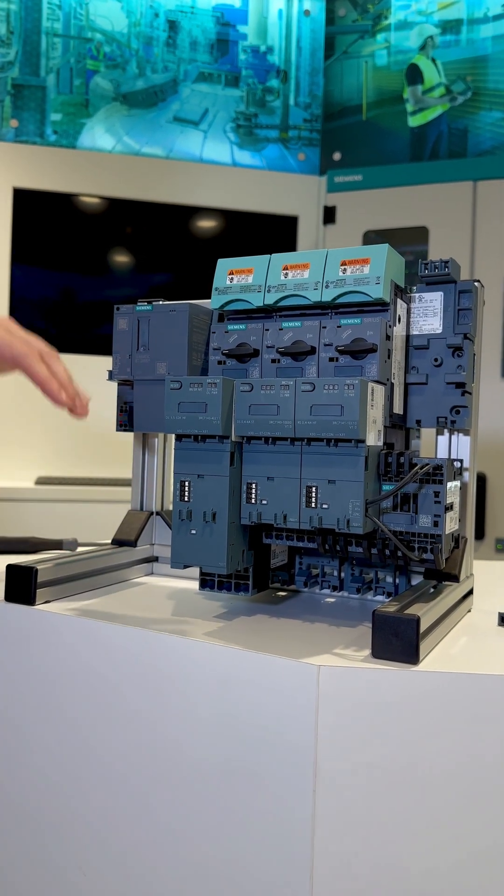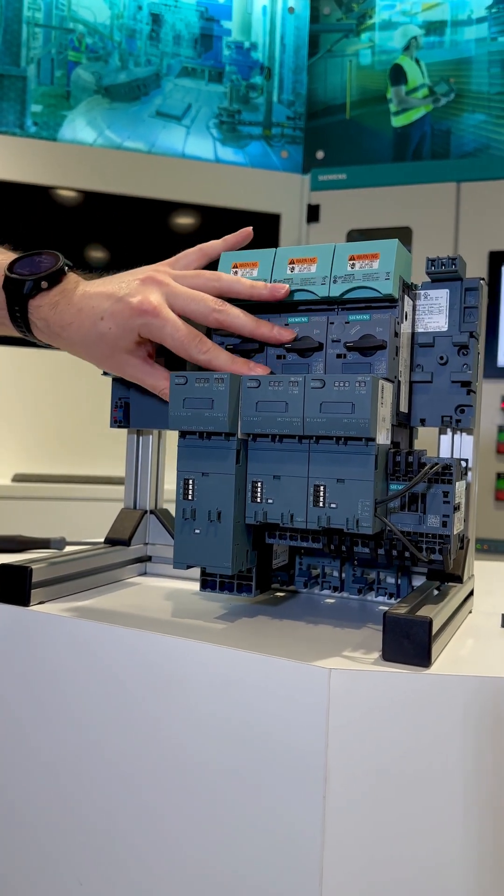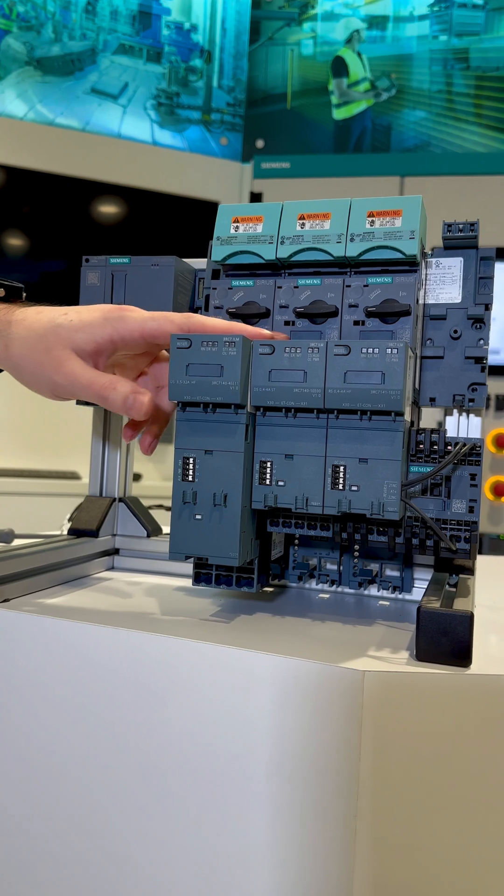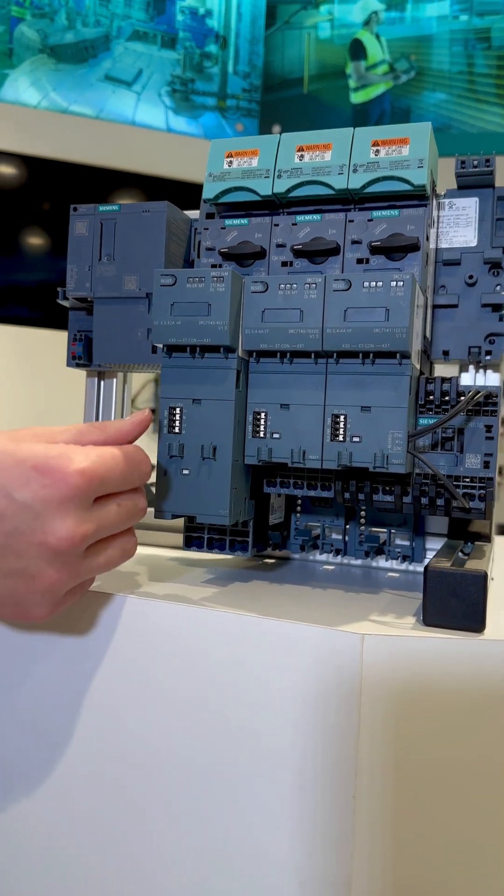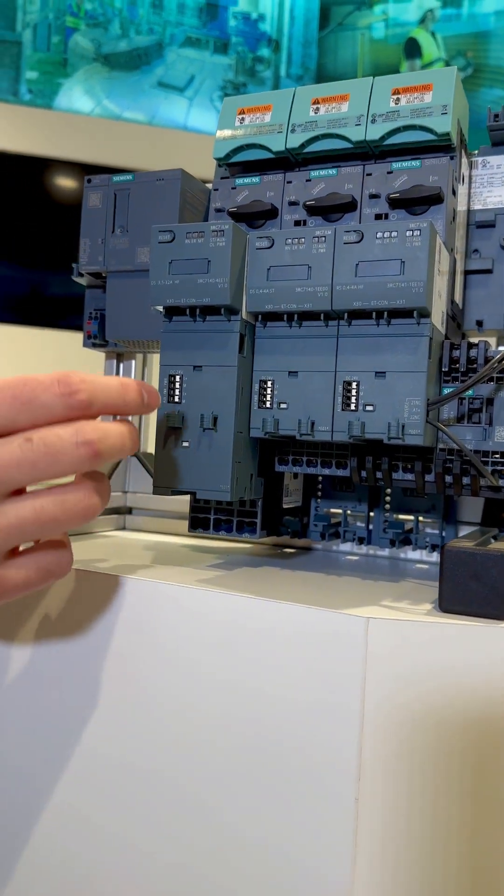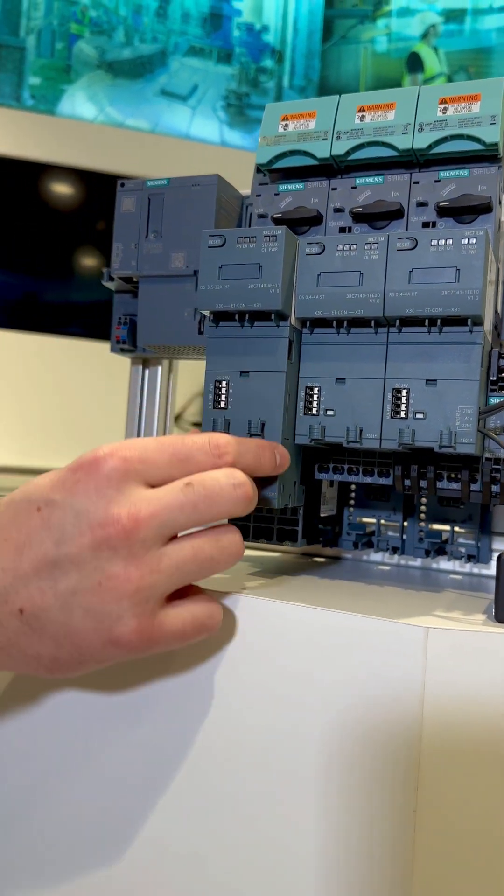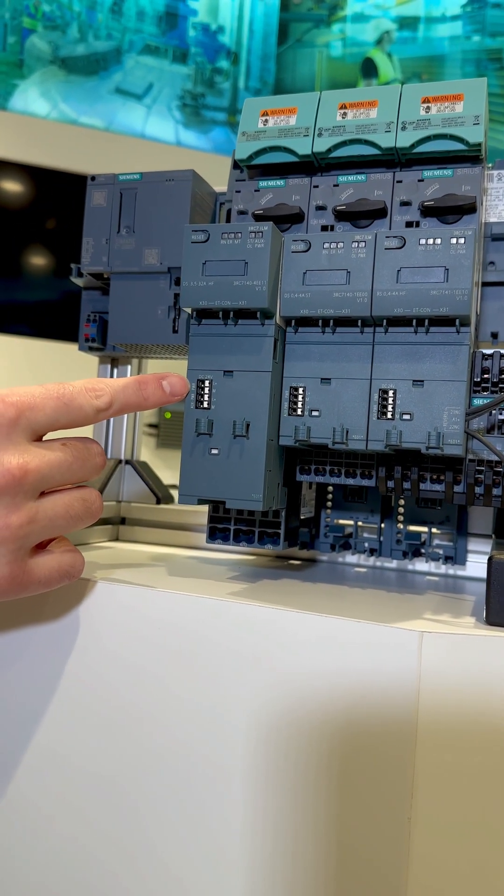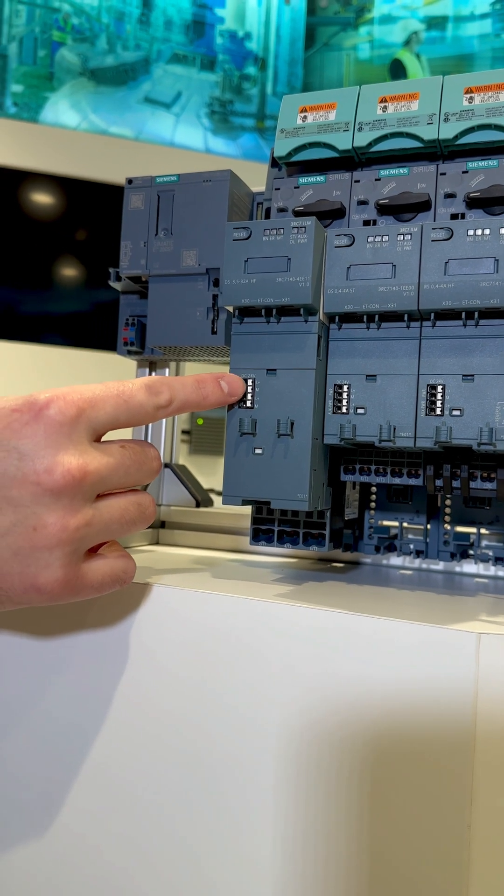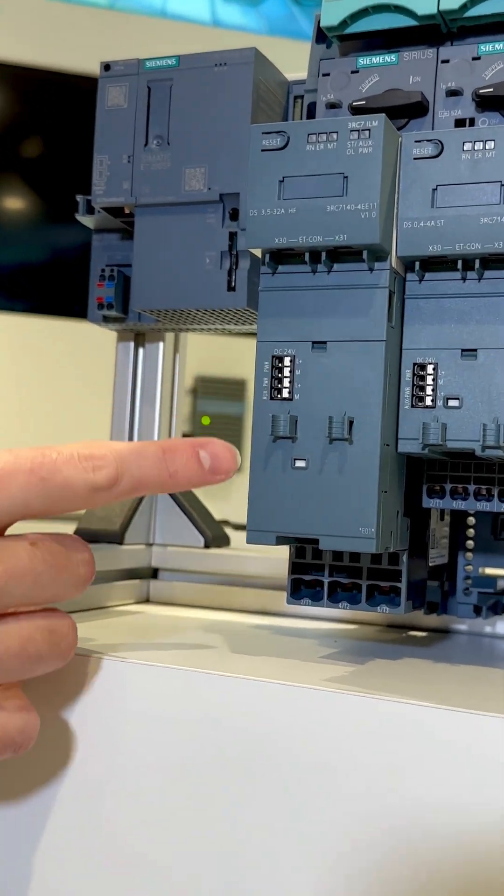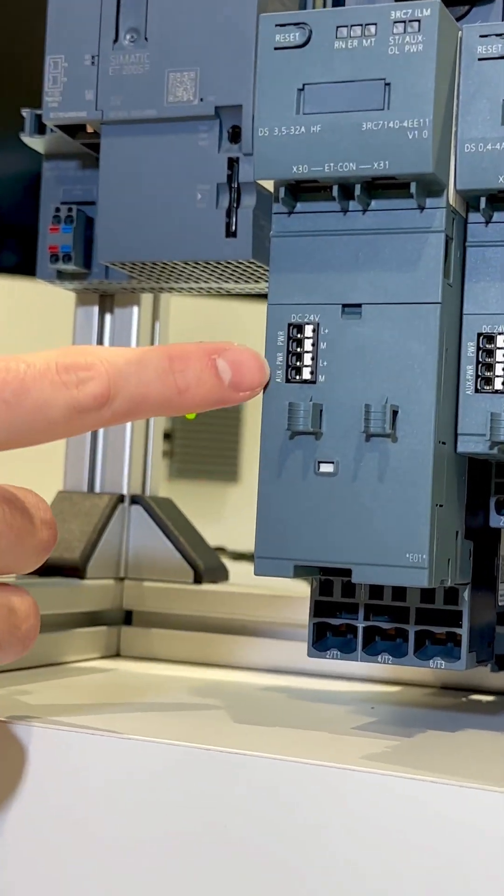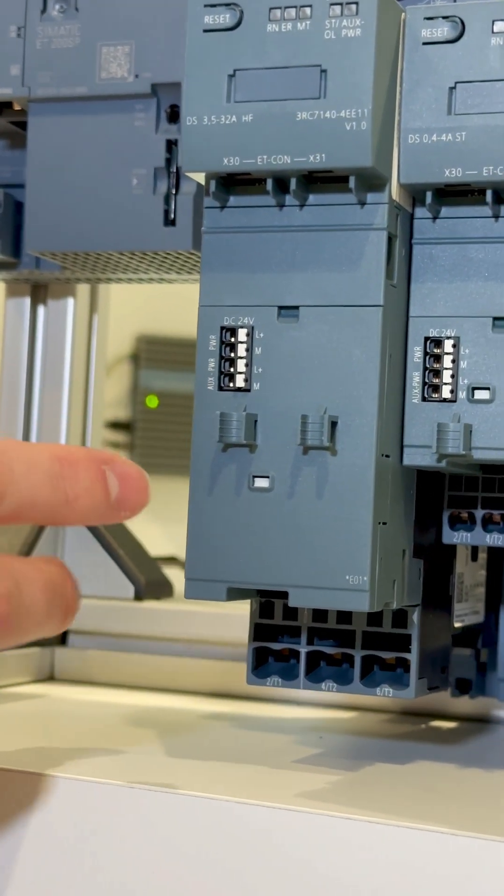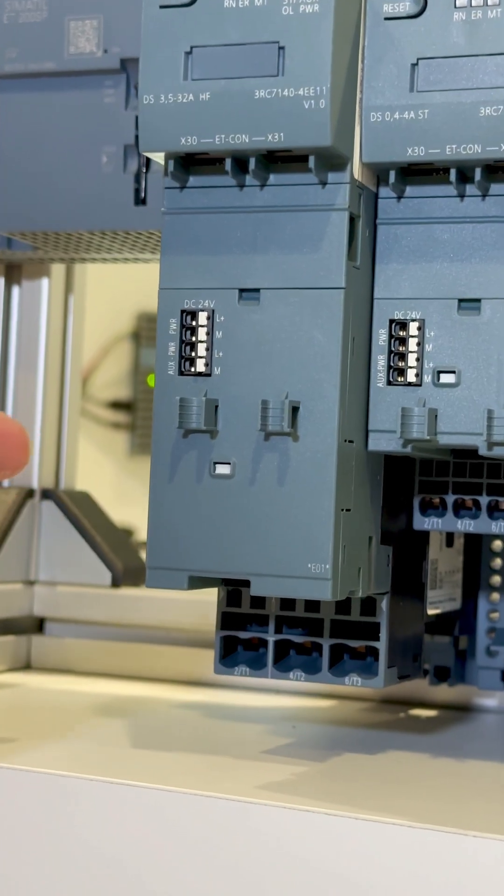Now we're going to take a look at the 3RC7's power cabling. On the front of the actual module itself, it requires its own 24 volt DC power, but then there's also the auxiliary power connection which feeds the 24 volt power through to the contactors.